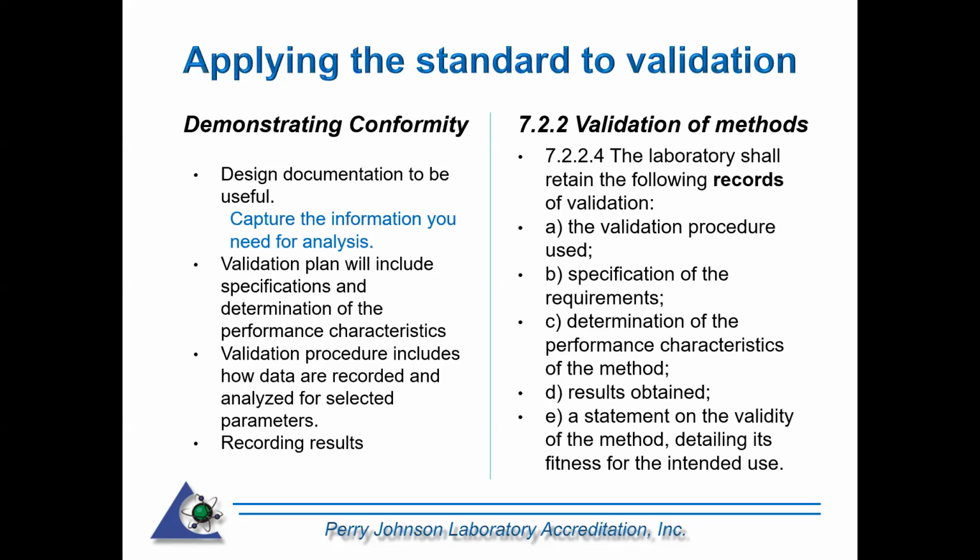Your validation plan will include the specifications and determination of the performance characteristics. Then there will also be the validation procedure, which will include how the data are recorded and then analyzed for the selected parameters. So you may do a calibration curve and determine the range that you want to be able to measure within. It needs to be a part of the procedure, the validation procedure, of what you are going to do with the data that you have, and how that data relates to the intended use.